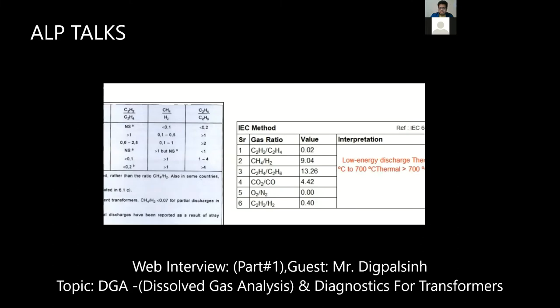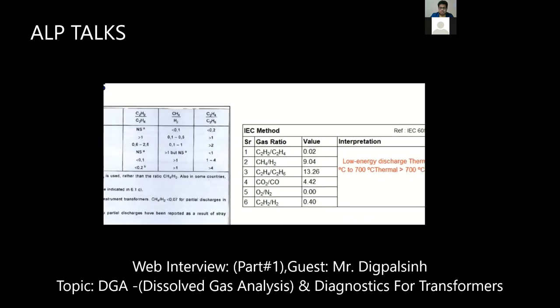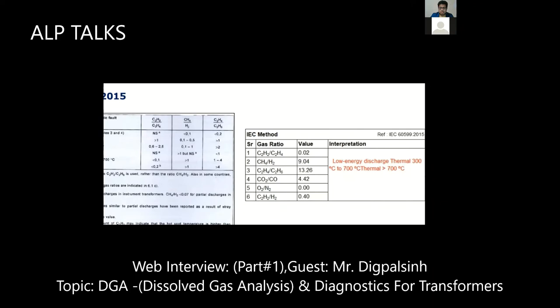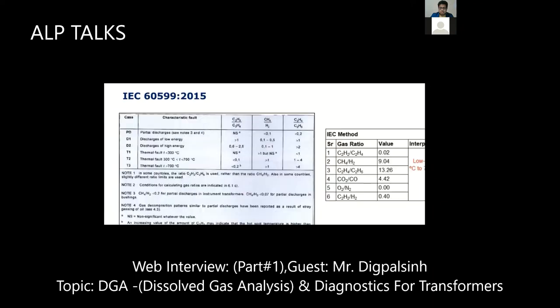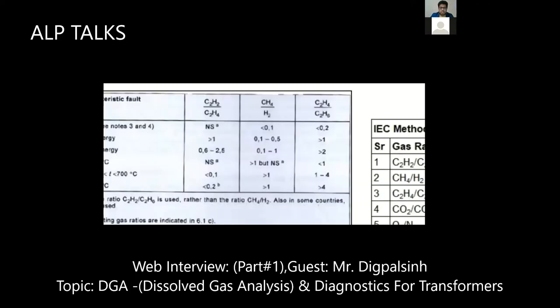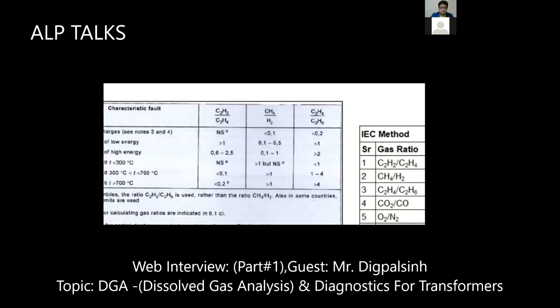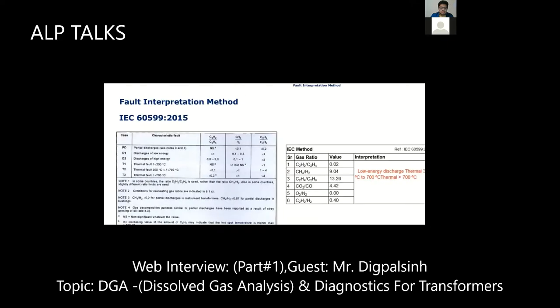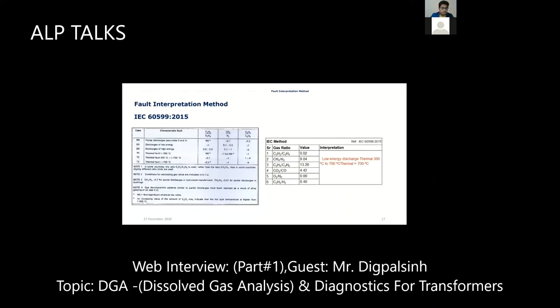C2H4 upon... similarly, CH4 upon H2, and C2H4 upon C2H6. If you count this value, it is beyond the value defined by IEC. So from this I can categorize it as a D1 and T3 fault.